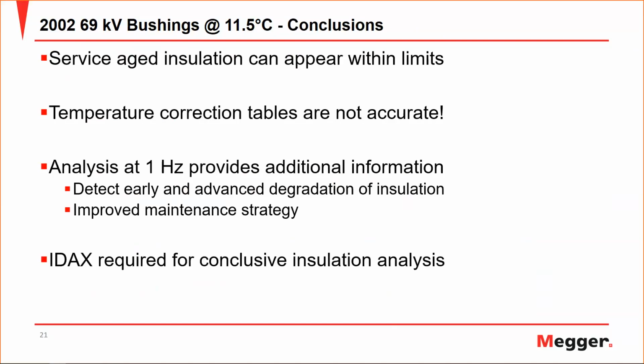What Megger has done with the Delta 4000 and the Trax Plus TDX is give you additional information beyond line frequency power factor using the same test set and same test connections. And when you look at 1 Hertz, we can tell you where best to focus your energy moving forward.